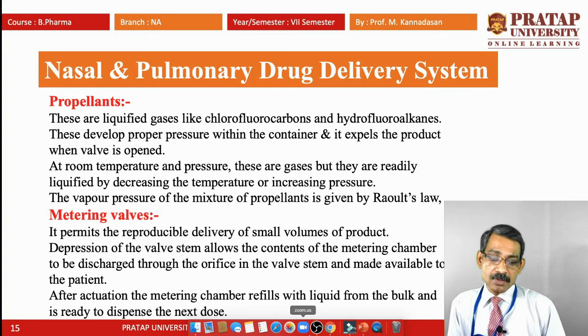Depression of the valve stem allows the content of the metering chamber to be discharged through the orifice in the valve stem and made available to the patient. After actuation, the metering chamber refills with the liquid. Once we press the valve, after delivering the drug, the dose is automatically refilled in the chamber. That is, after actuation the metering chamber refills with liquid from the bulk and is ready to dispense the next dose.